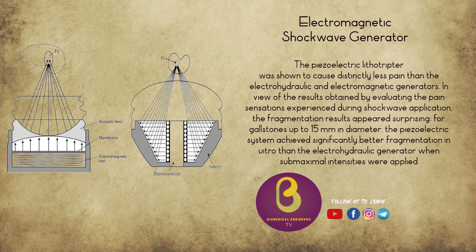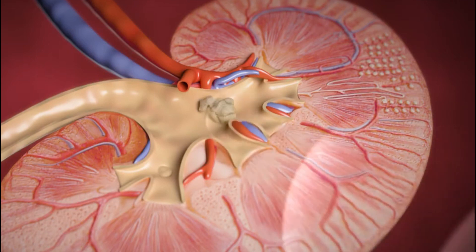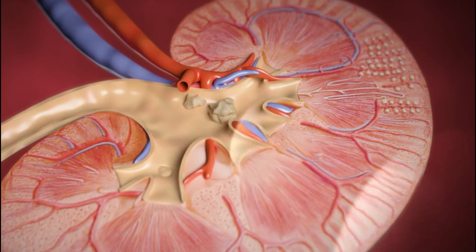The third type of shockwave generator is electromagnetic. In an electromagnetic generator, a high voltage is applied to an electromagnetic coil, similar to the effect in a stereo loudspeaker. This coil, either directly or via a secondary coil, induces high frequency vibration in an adjacent metallic membrane. This vibration is then transferred to a wave propagating medium — water — to produce shockwaves.